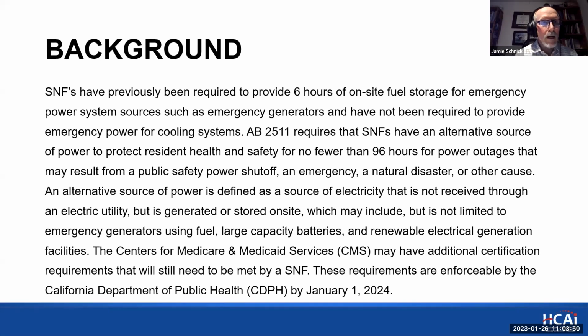As brief background, SNFs are regulated, and HCAI oversees the construction design of those facilities. Previously, the code only required 6 hours of on-site fuel storage for emergency power systems, and the code-mandated backup did not include cooling equipment. So this new requirement adds cooling, which is typically not on emergency power, and extends the requirement from 6 hours to 96 hours.